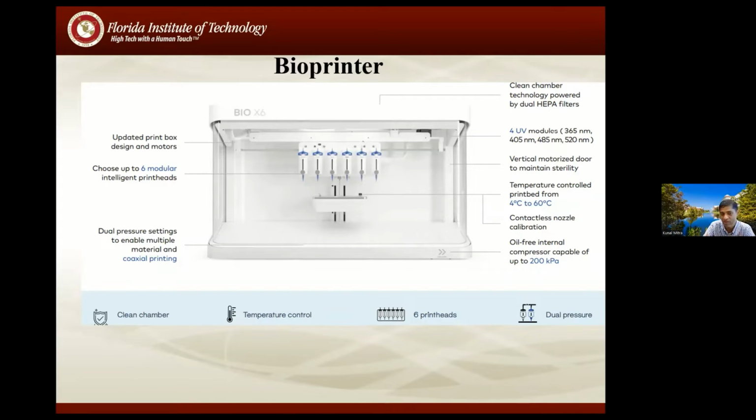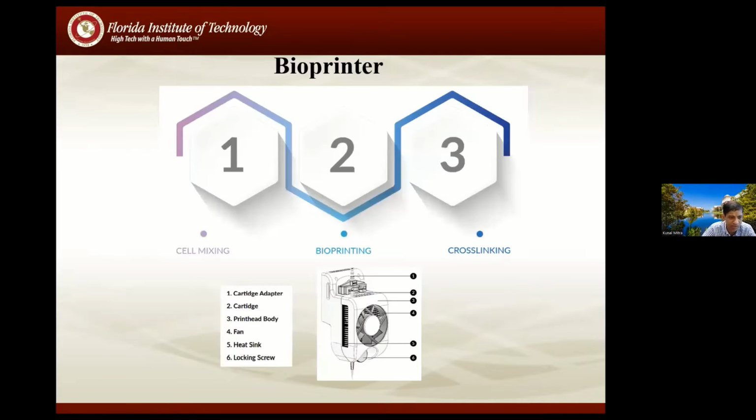So these characteristics have to be really well controlled, and that's why you could see that the print head bed temperatures can range quite high. I mean, we definitely never go to 60 degrees, but it has the potential. But typically, with our controls, we have anywhere from 10 degrees to 25, 30 degrees based on what type of biomaterials we are using. So it's a lot of controls and optimization, and the pressures involved in this 6-head bioprinting process.